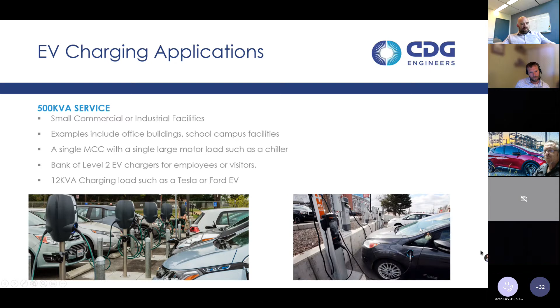So these would be about a 12 kVA charging load like you'd see from a Tesla or Ford EV - we just looked at their cut sheets and used that as an example. Running that in ETAP, this is an example one line. When you run your load analysis, here we have your MCC, your large motor load, and your 500 kVA transformer.